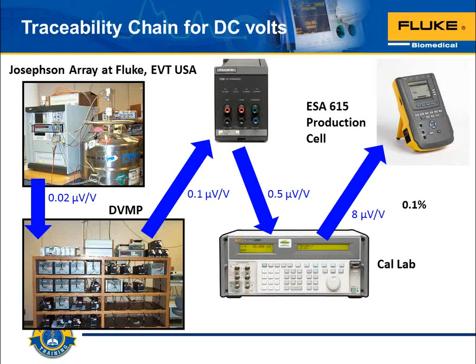And so you see the stack up of uncertainties, and we keep it purposely very, very small so that during the calibration cycle of the test instrument that you get from us, you can rely on the fact that it's going to stay within its tolerances during that calibration cycle. And we really won't extend that calibration cycle. We prefer not to when we have our choice of the matter, because it's how we assure you that you're going to get the performance out of our test instrument.